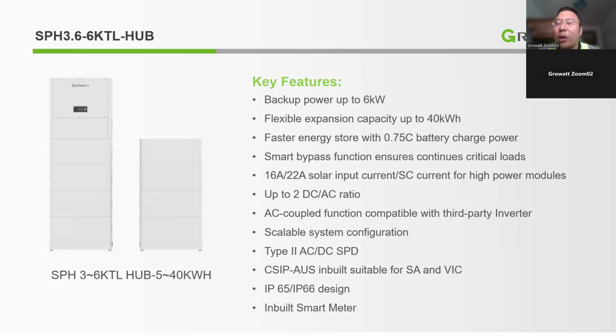The most critical problem right now for inverters with inbuilt ATS or EPS function is, hypothetically, if the inverter is dead or under maintenance, there will be no power supply for the critical EPS load. Based on this, we developed 2 types of solutions. The first is the software part: if our inverter realizes it's going to have a big problem, it will automatically switch back by itself internally from the EPS power support to the AC grid.